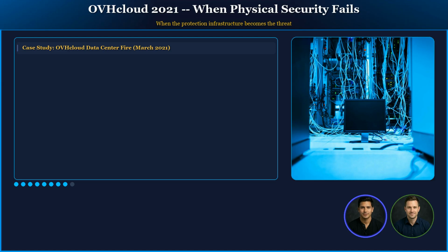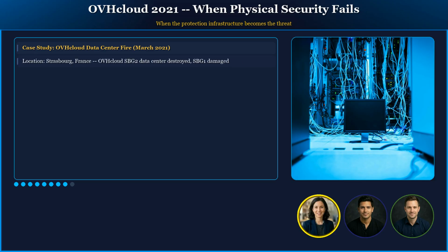In March 2021, OVH Cloud's SBG2 data center in Strasbourg, France was destroyed by fire. The adjacent SBG1 facility was partially damaged. OVH Cloud is one of Europe's largest cloud providers, and thousands of customers lost data, some permanently. The fire is believed to have originated in a UPS unit, precisely the component designed to protect against power failures. The fire spread rapidly through the facility due to the high density of cabling and inadequate fire compartmentalization between server rooms. The fire suppression system was simply not adequate for the density of equipment and cabling in the facility.